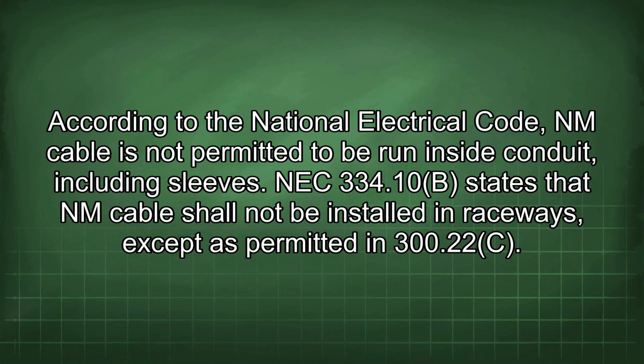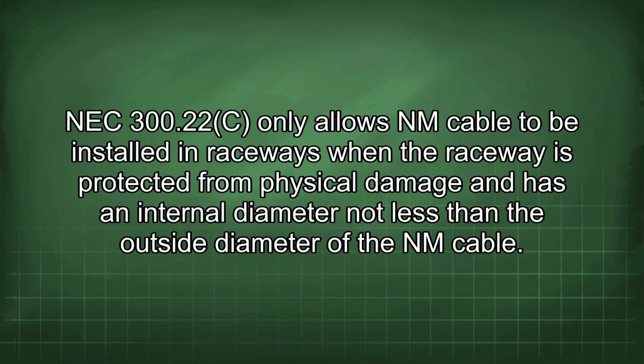According to the National Electrical Code, an NM cable is not permitted to be run inside conduit, including sleeves. NEC 334.10(B) states that an NM cable shall not be installed in raceways except as permitted in 300.22(C). NEC 300.22(C) only allows an NM cable to be installed in raceways when the raceway is protected from physical damage and has an internal diameter not less than the outside diameter of the NM cable.